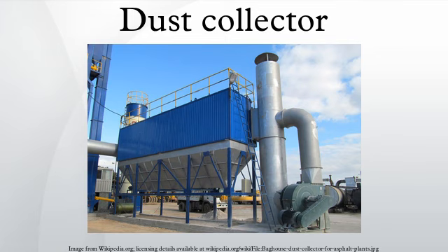Pre-coating. To ensure the filter bags have a long usage life, they are commonly coated with a filter enhancer. The use of chemically inert limestone is most common as it maximizes efficiency of dust collection via formation of what is called a dust cake or coating on the surface of the filter media. This not only traps fine particulates but also provides protection for the bag itself from moisture, and oily or sticky particulates which can bind the filter media. Without a pre-coat, the filter bag allows fine particulates to bleed through the bag filter system, especially during startup, as the bag can only do part of the filtration, leaving the finer parts to the filter enhancer dust cake.